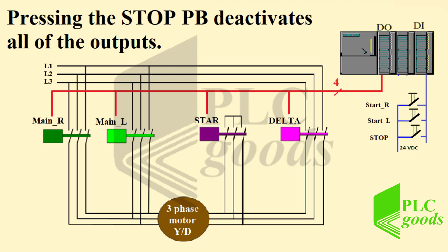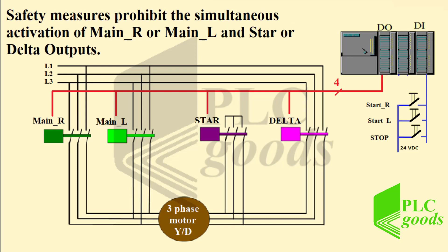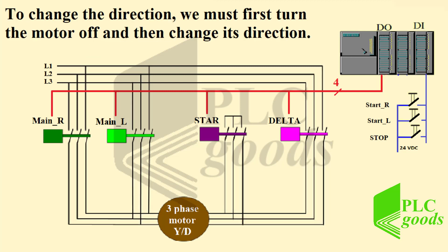On the other hand, pressing the stop push button deactivates all of the outputs. Safety measures prohibit the simultaneous activation of main right or main left and star or delta outputs. To change the direction, we must first turn the motor off and then change its direction.